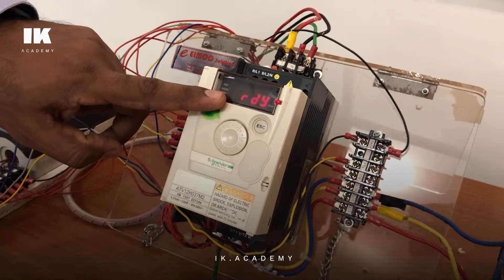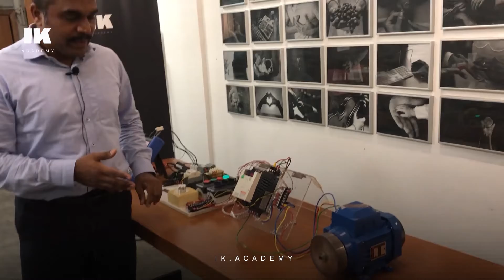Then I'm going to give a signal. For example, if the PLC is connected to a variable frequency drive, the PLC has to give a running signal. So I'm giving a running signal. You can see that the motor is running. And the best thing, as you know, about a variable frequency drive is that you will be able to control the speed. As you can see now, the motor speed is very low. It's about 14 hertz now, right? And obviously I can increase the speed to the maximum. In this case, we fix it to 50 hertz.